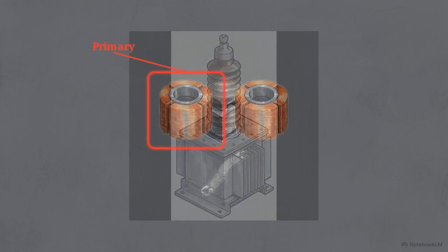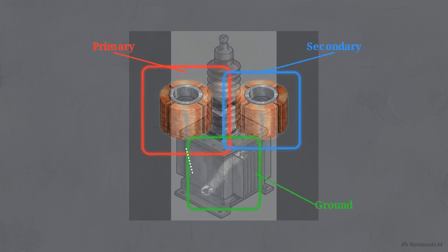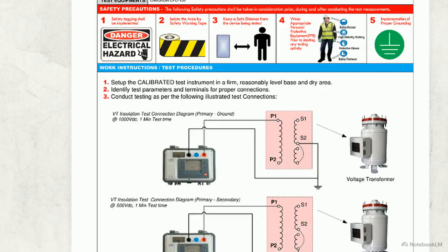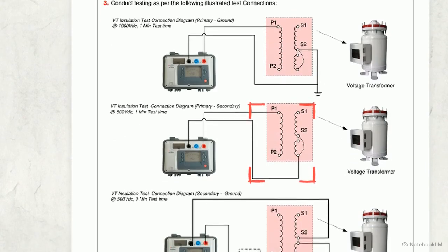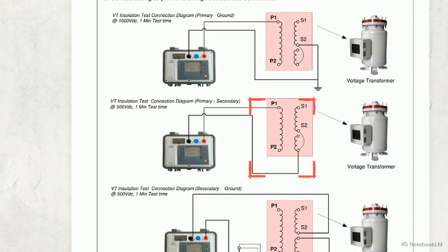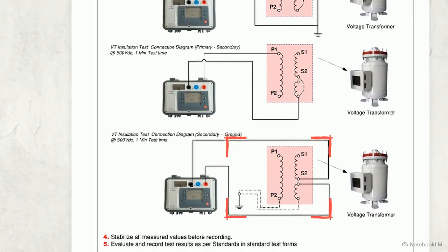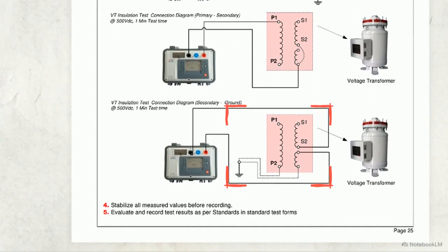We need to verify the insulation separating the primary windings, the secondary windings, and the ground boundary before any functional voltages are applied. As this schematic shows, operators first test the primary to ground boundary by injecting a direct current of 1,000 volts. Next, connections are shifted to measure the primary to secondary boundary at 500 volts DC. Finally, the secondary to ground boundary is tested, again at 500 volts DC.